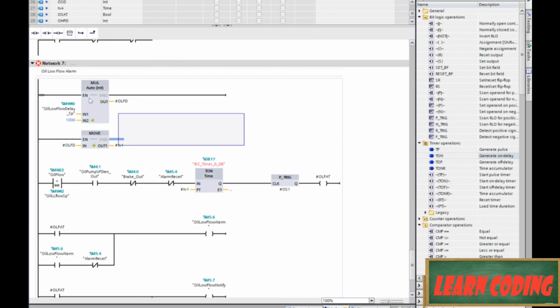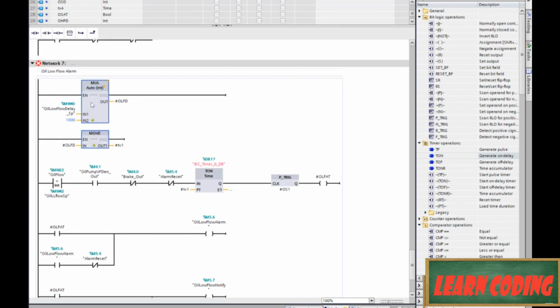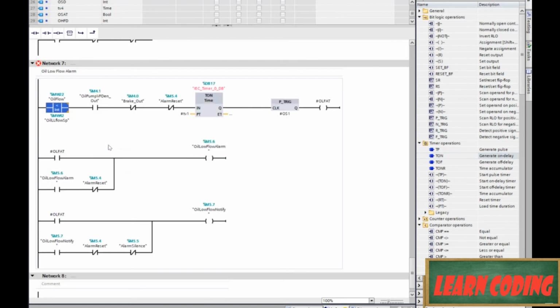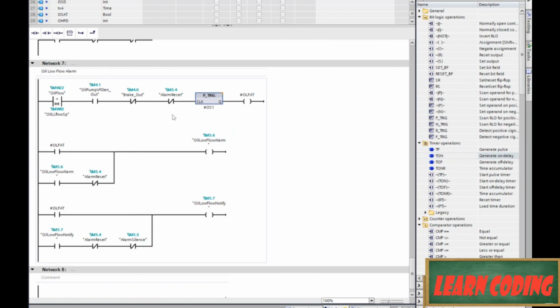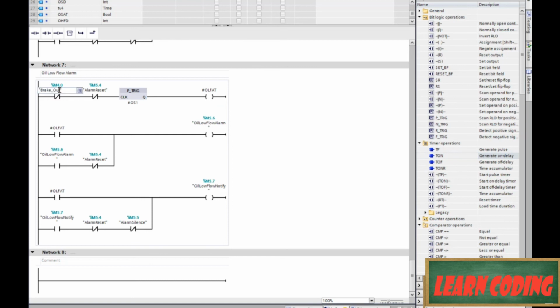Okay, 6 down, 1 to go, and this one's going to be our EStop. Guess what that means? All of this stuff right up here, we can delete. Oops, if it lets me. Right click all that, delete. There's not going to be any time on this guy, so we can get rid of that timer. And actually, we're going to keep one of those and get rid of both of these. So we're looking for our EStop, and in this case we want our EStop to be closed or open, and that's going to be the alarm. So when it's closed, everything is good.